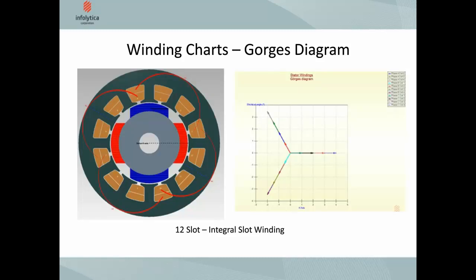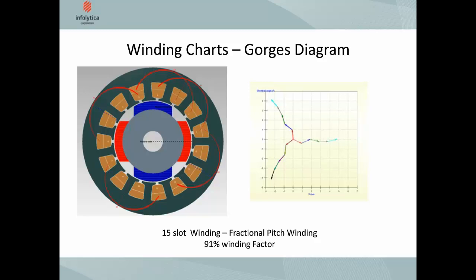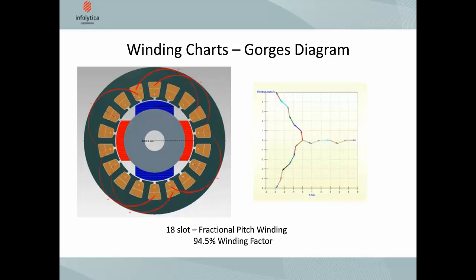Here's an example of using the Gorges diagram. For a full pitch integral slot 12-slot winding, you have an ideal star diagram. For a 15-slot motor, the diagram is no longer perfectly star-shaped — it has some excursions from the straight line along each phase. An 18-slot winding has a better winding factor of 94.5% and is closer to an ideal waveform. The Gorges diagram is quite useful for seeing how well your winding matches the ideal three-phase star winding.